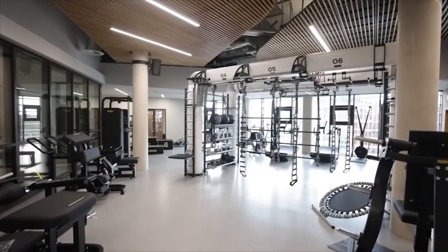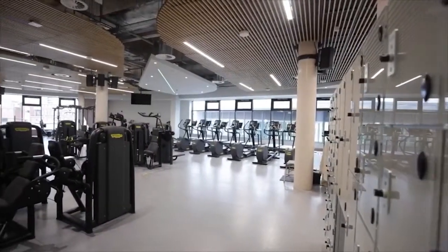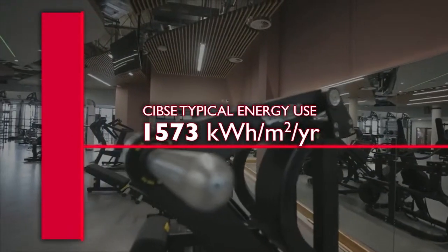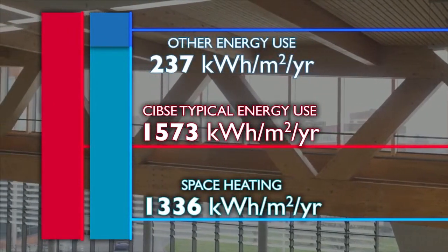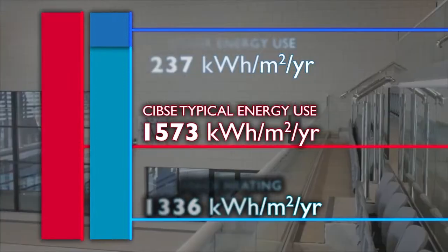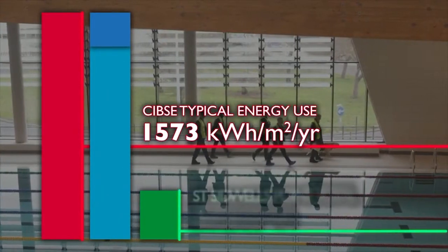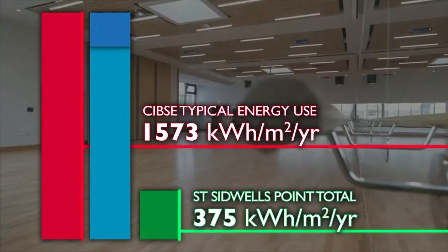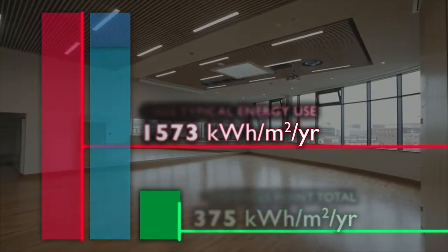Leisure facilities and particularly swimming pools are usually the most energy intensive buildings in a local authority's stock, so reducing consumption can have a major impact on an authority's energy footprint. According to CIBSE, a typical leisure centre will consume 1,573 kilowatt hours per metre squared per year, of which 237 kilowatt hours is electricity for lighting and services while 1,336 kilowatt hours is used for space heating. In contrast, the target energy use for St Sidwell's Point is just 375 kilowatt hours per square metre per year — a 76% reduction over a typical design and almost half the energy use of even recent best practice.